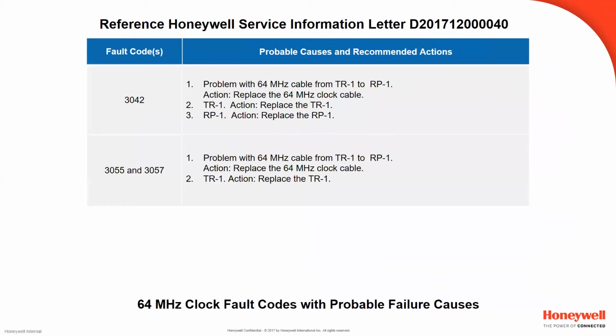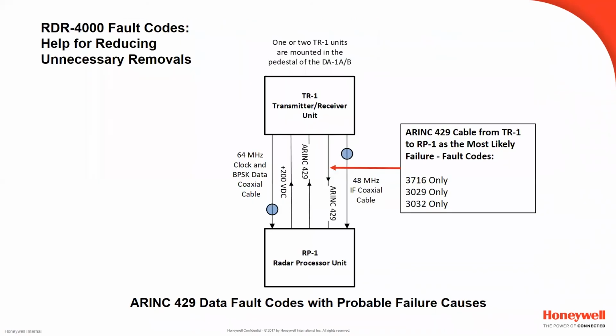Only if the fault continues even after cable replacement, then we recommend to replace the TR. We usually see for these two fault codes logging together that customers replace both RP and TR together, wherein it would lead to no fault found of both these components. And we're moving to the next.